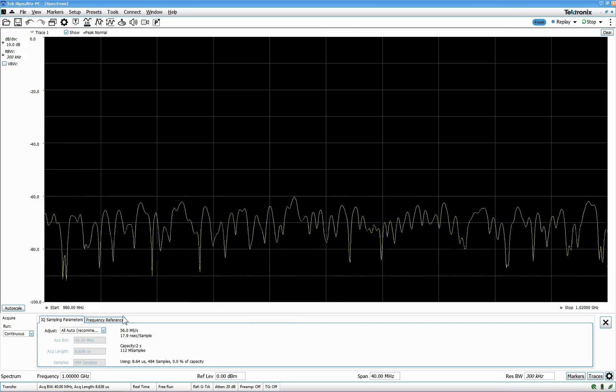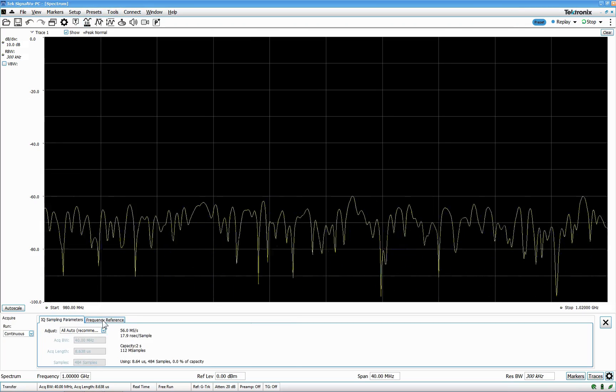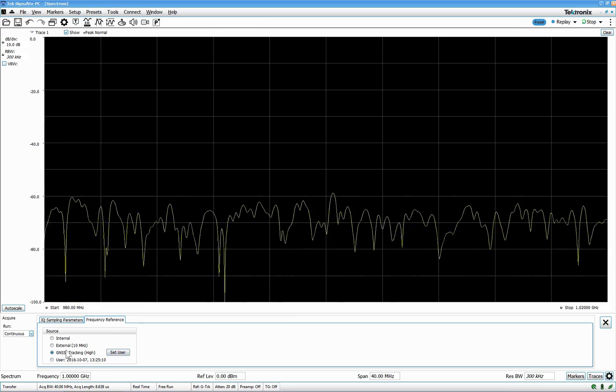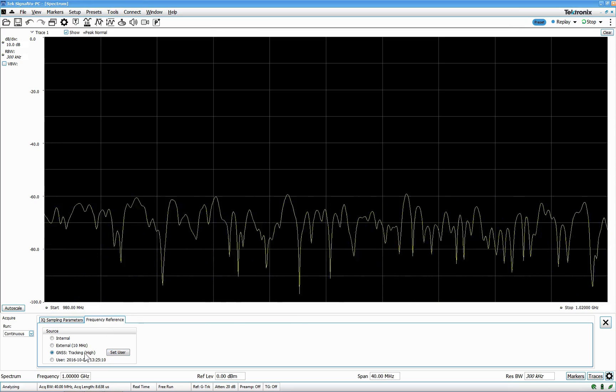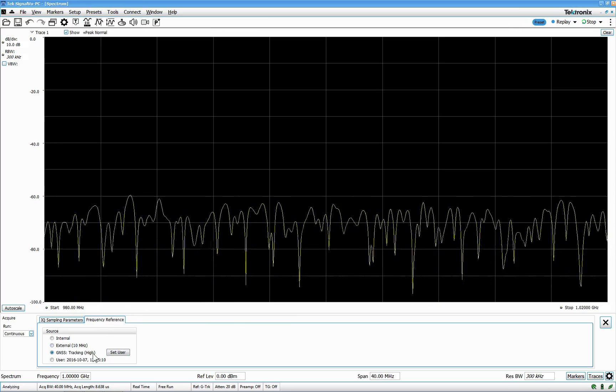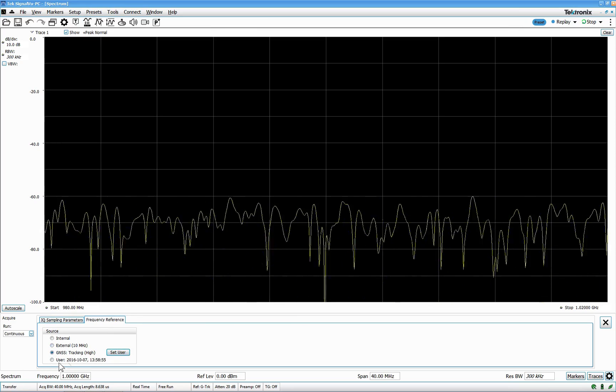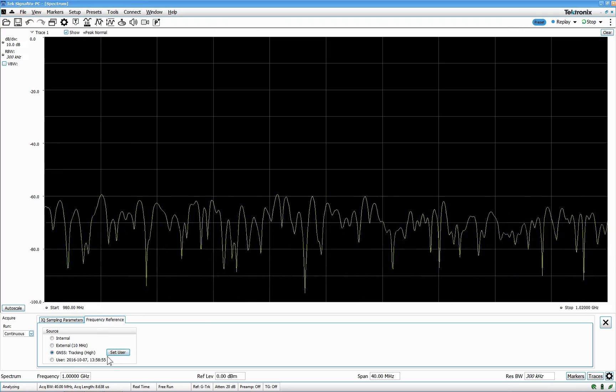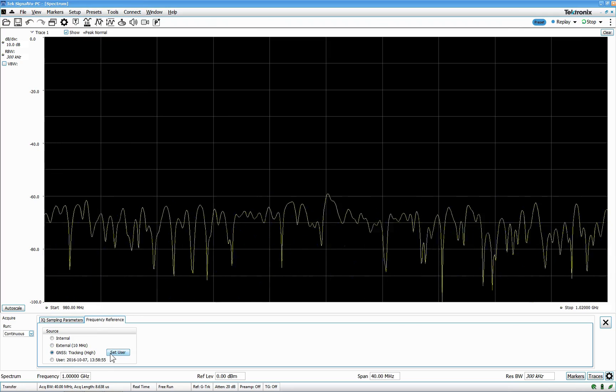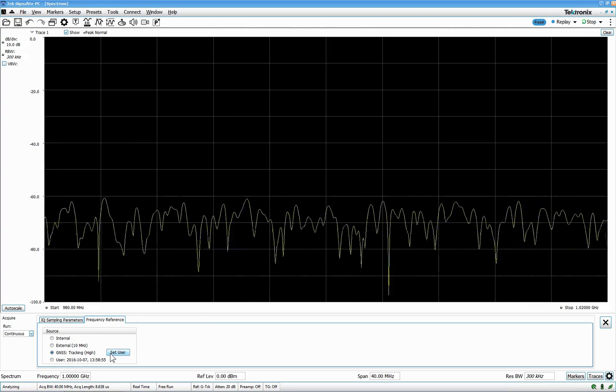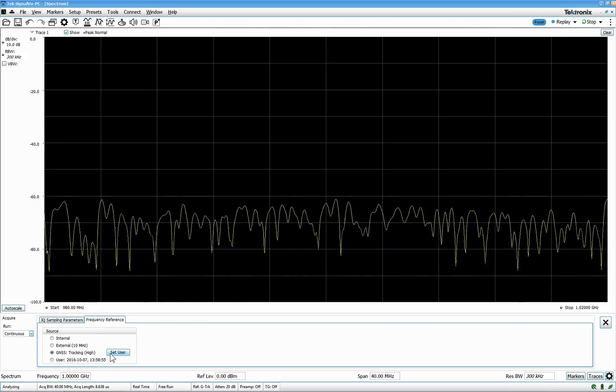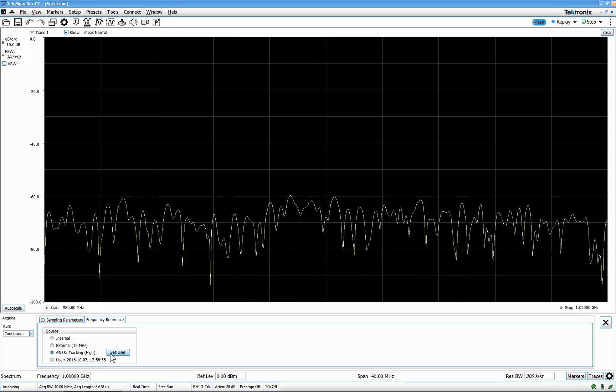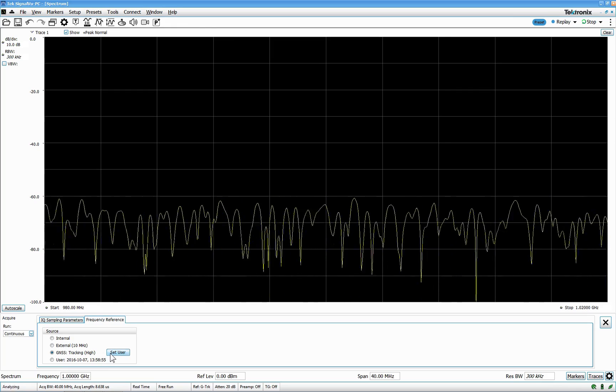If you go for the GPS here in the acquisition control menu on the frequency reference, you can use this tracking. There's a high tracking you can set. This means that the absolute frequency measurement is much better, instead of 1 ppm it's 0.025 ppm.